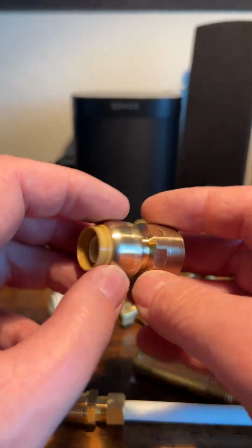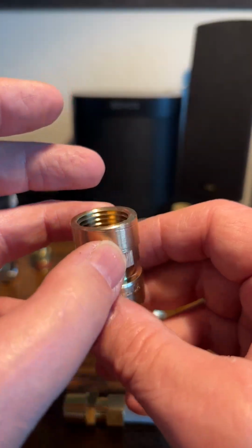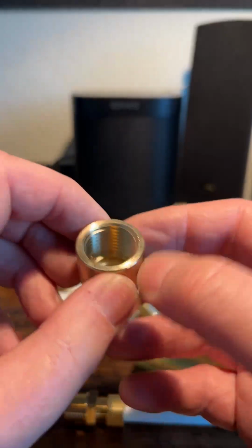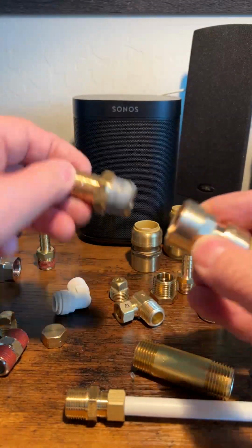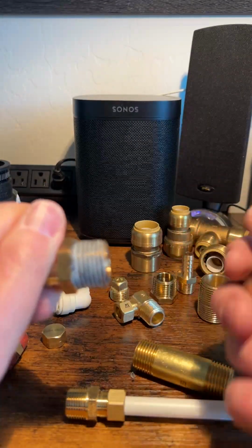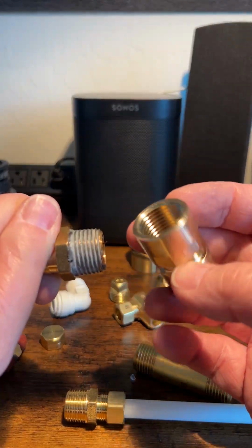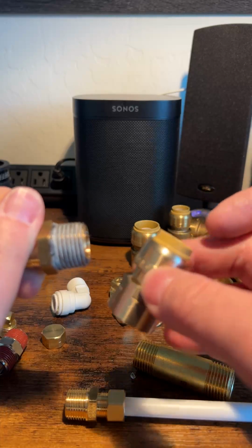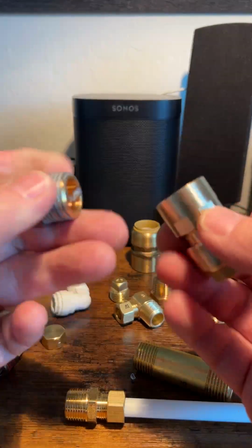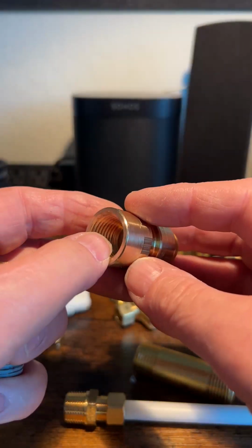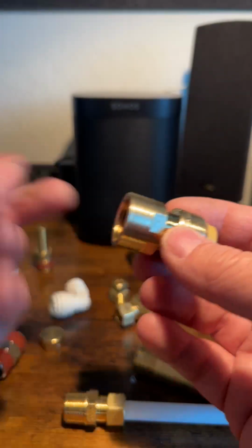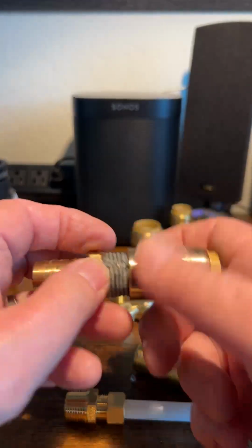So if you needed one of these, I need to order it without a picture, what would you order? I know I need 1/2 inch pipe. So I need a female, if I'm connecting to this piece right here, I need something female to connect to that. So I need a female 1/2 inch by, if you want to use PEX, by push fitting. So you would order a 1/2 inch FIP by 1/2 inch push fitting to get that job done, right?